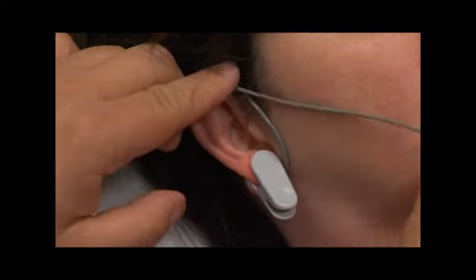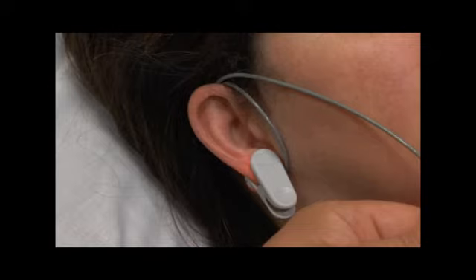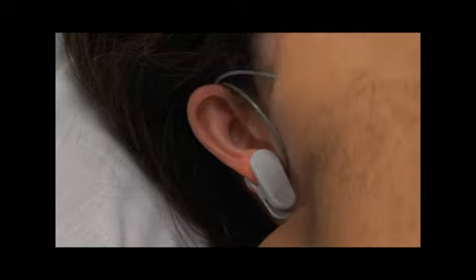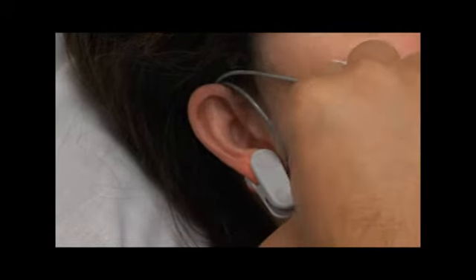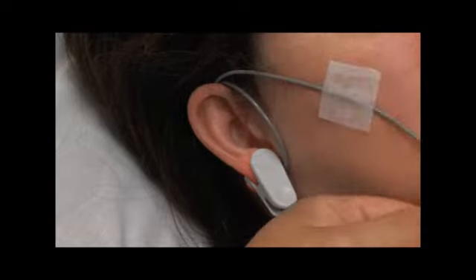Make sure that the sensor has good contact to the skin with no air gaps between the membrane and the earlobe. Wrap the sensor cable around the ear once. Tape the cable to the cheek and secure the cable with the clothing clip on the patient's shirt or bed linen.